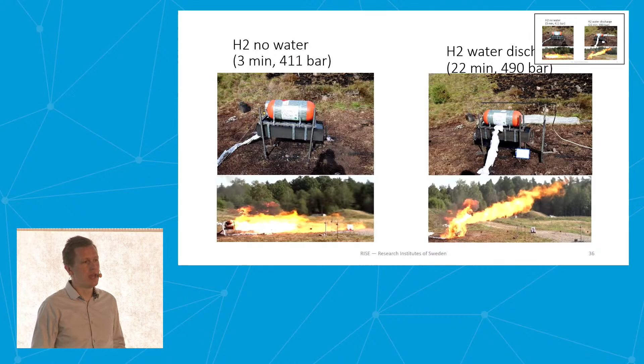Just showing one result with the hydrogen tank: you see the pan underneath with the external fire, and then we had a sprinkler or water on top of the tank. With water discharge, you delay the ventilation by 20 minutes. We also had a scenario where the tank was shielded and water was only applied to the temperature-controlled safety vent, to see if that could cause an explosion of the tank.